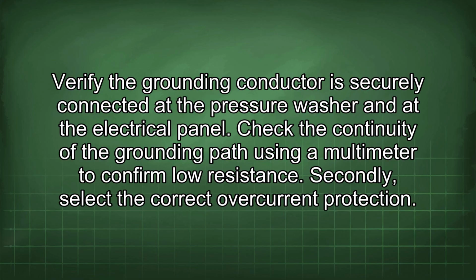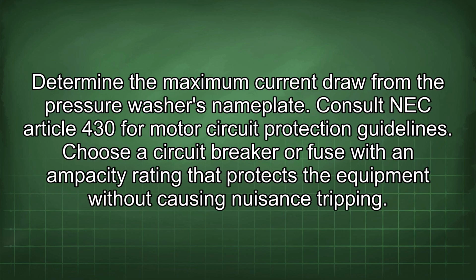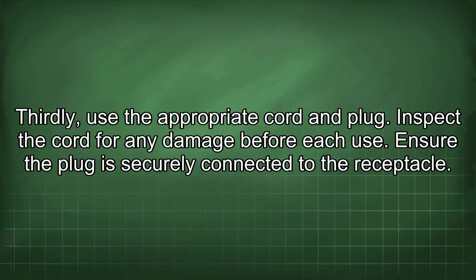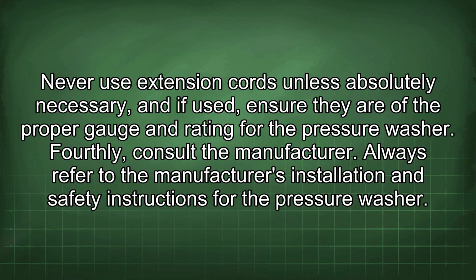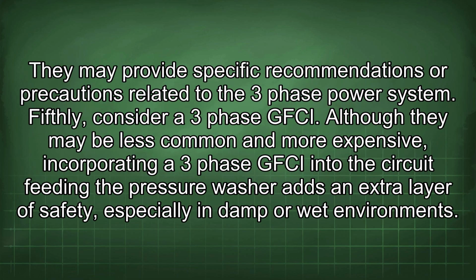Secondly, select the correct overcurrent protection. Determine the maximum current draw from the pressure washer's nameplate. Consult NEC Article 430 for motor circuit protection guidelines. Choose a circuit breaker or fuse with an ampacity rating that protects the equipment without causing nuisance tripping. Thirdly, use the appropriate cord and plug. Inspect the cord for any damage before each use. Ensure the plug is securely connected to the receptacle. Never use extension cords unless absolutely necessary, and if used, ensure they are of the proper gauge and rating for the pressure washer. Fourthly, consult the manufacturer. Always refer to the manufacturer's installation and safety instructions for the pressure washer. They may provide specific recommendations or precautions related to the three-phase power system.